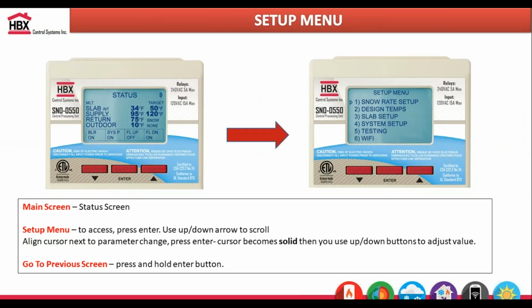On the controller, it'll tell you your slab temperatures and targets. It'll tell you your system temperature. It will actually tell you if the sensor is picking up any snowfall. To navigate with our controllers with the 550, it's just up and down or enter. If you hold the enter button down for 2 seconds, it'll take you into a setup menu screen.